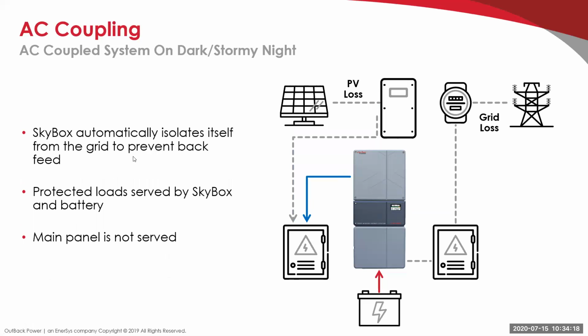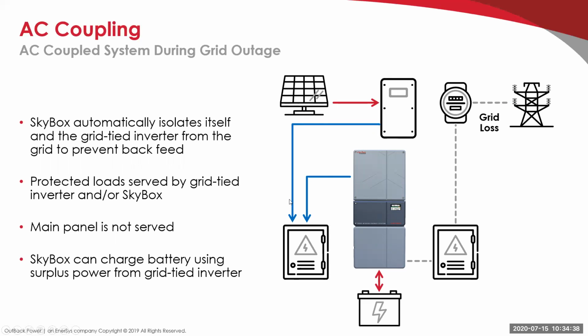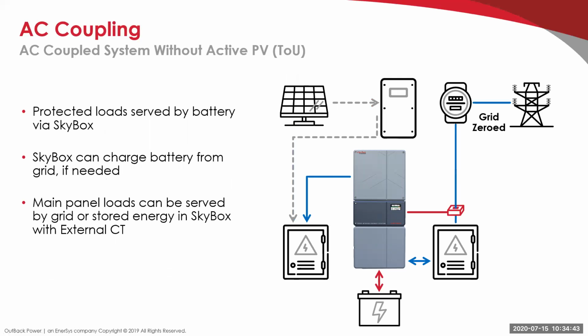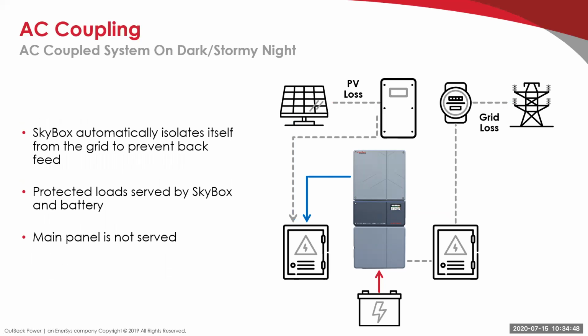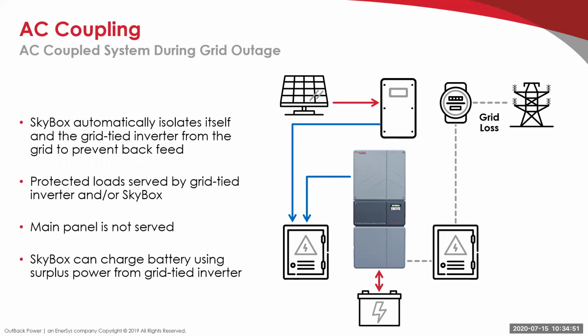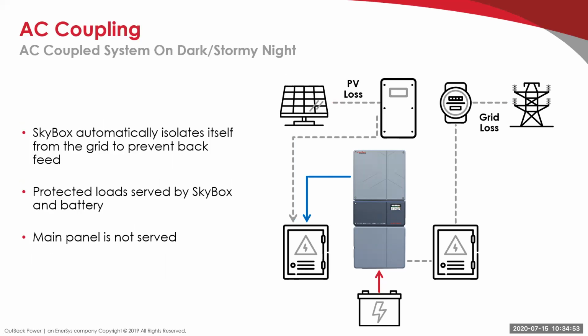With grid loss, when the sun goes down in the evening, power comes solely from the inverter, taking energy from the battery to power the loads until the next day when the sun comes out, and the cycle repeats. This will continue switching back and forth until the grid comes back online.